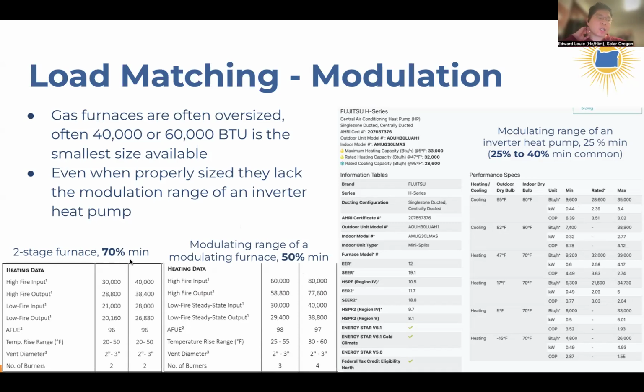Because, as I said, the smallest furnaces out on the market are around 40,000 or even 60,000 BTUs. And so the question remains: if you're saying that a lower output to match the heating needs of the building on a mild day is good for comfort, then wouldn't that be good enough to get a two-stage furnace or even a modulating furnace? And yeah, that might be okay.